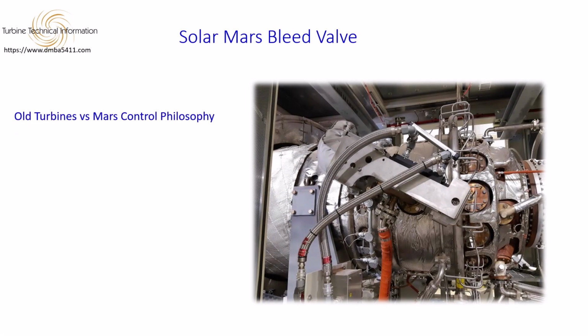Old turbines versus Mars control philosophy. If you've worked on Centaurs or Saturns, you remember the old style. Bleed valves were open or closed, digital control and fixed speed references. Why did that work? Those turbine compressors had big surge margins, and were forgiving. The Mars is a high-performance compressor. High efficiency. Tight surge margin. It needs a modulating valve and a scheduled ramp. That's the price of performance.